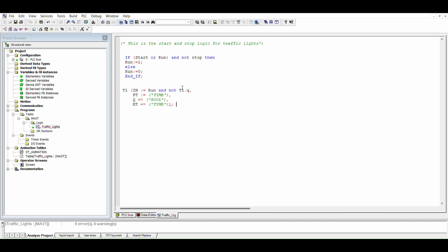So now the timer is continuous from 0 to 70 seconds and goes back to 0 because of this. So I'm going to use the PT, like I said, T hashtag 70 seconds. That's the format you use for a timer in ST, structured text language. So I'm going to say this one is the output. I think I have that variable already. And I'm going to say ET.